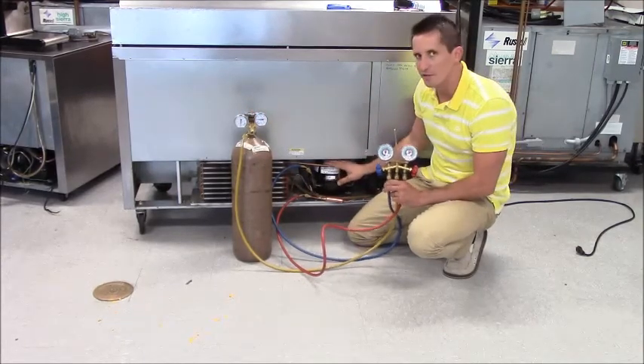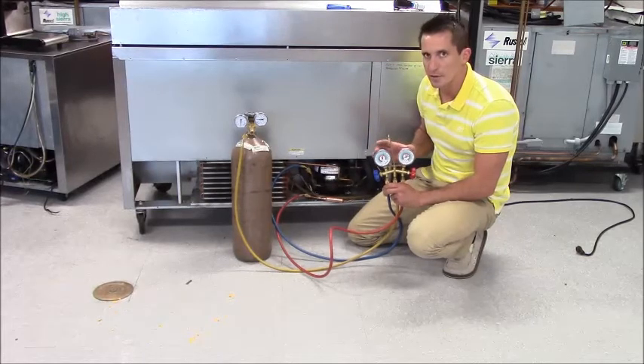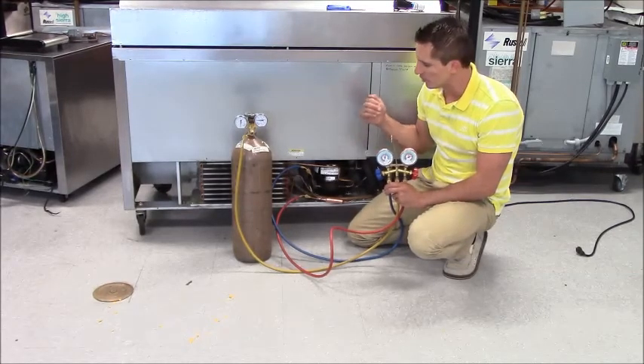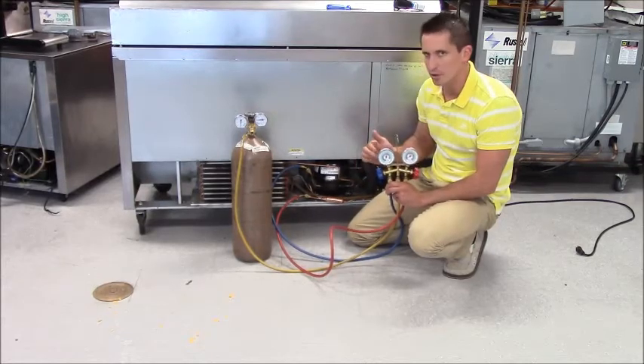All the refrigerant is already recovered from this unit. Both my gauges should be at zero. What I'm going to do now is pressurize the high side with a little bit of nitrogen. That nitrogen is going to flow through the high side, flow through your cap tube, and pressurize your low side.